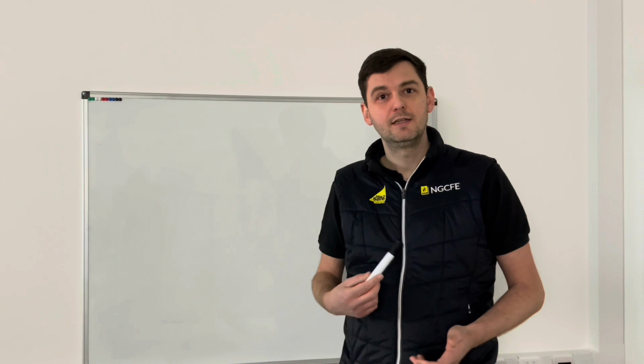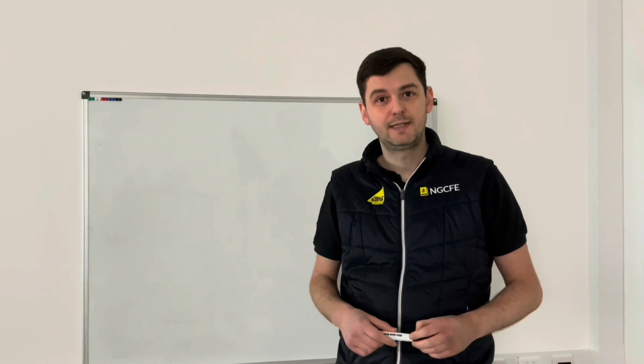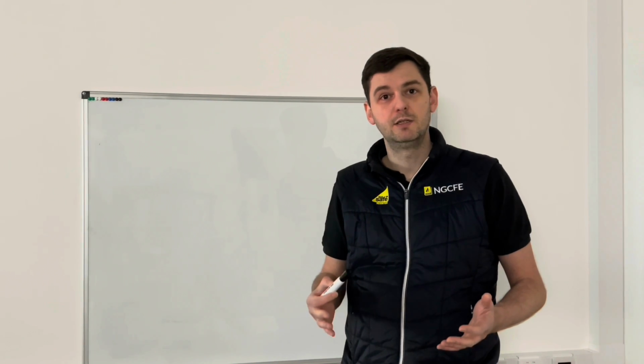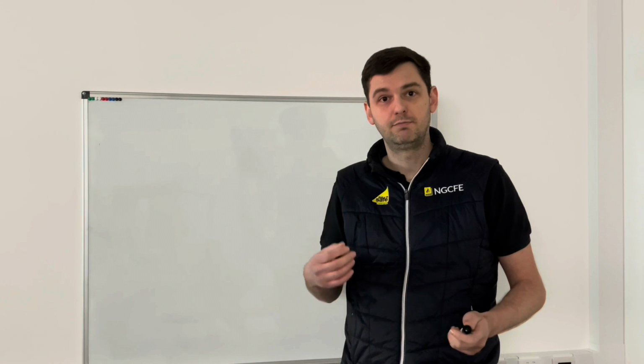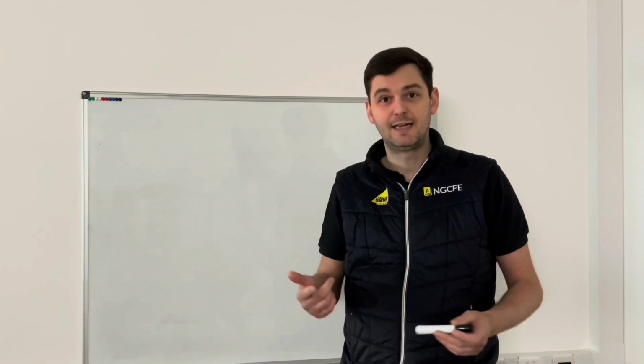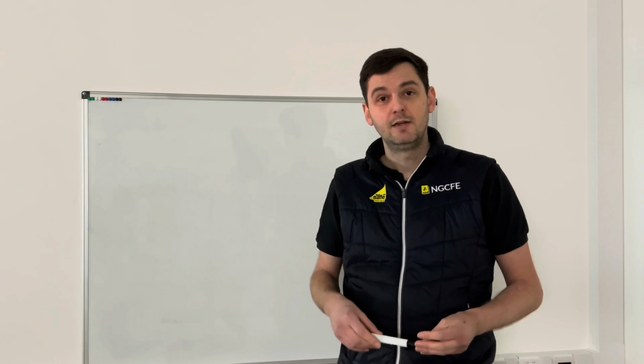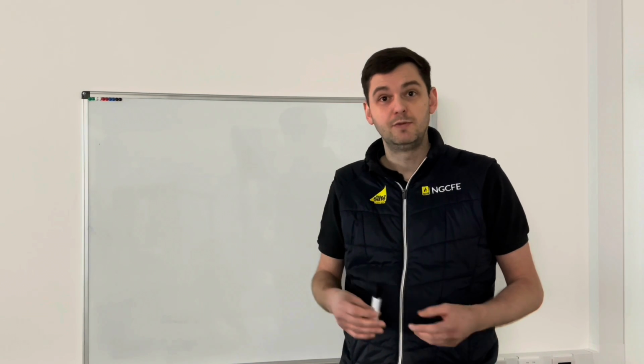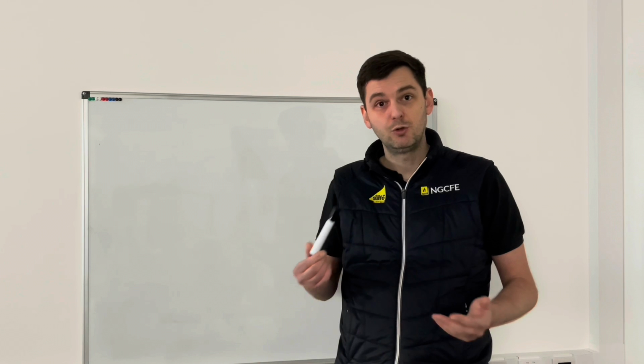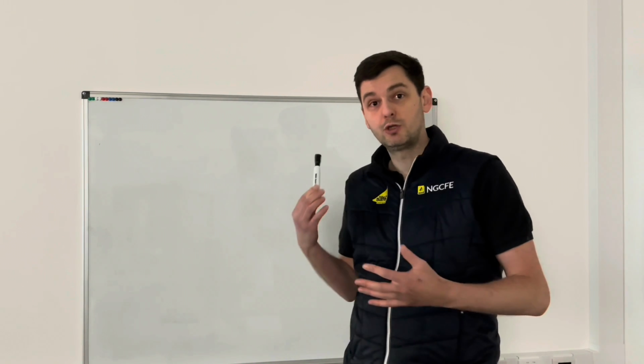Thank you, Alan. So today we're going to talk about flame rectification. We've all been to boiler faults that have been showing flame failure, ionisation faults. A potential cause of that is flame rectification. Flame rectification is a type of flame supervision device, and ultimately we're going to talk about it on the board.